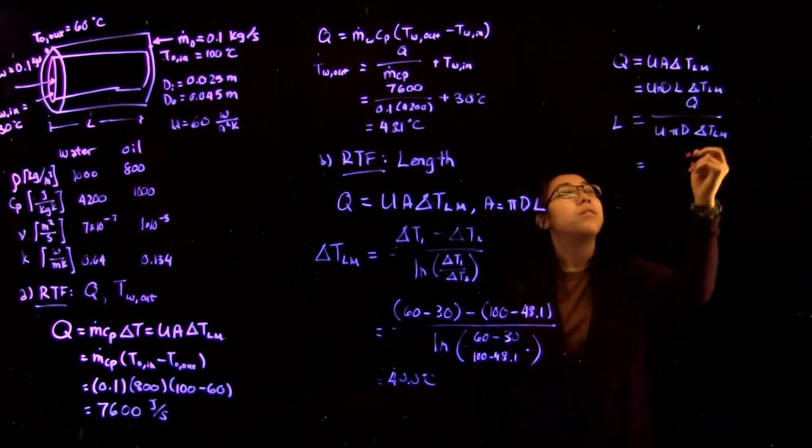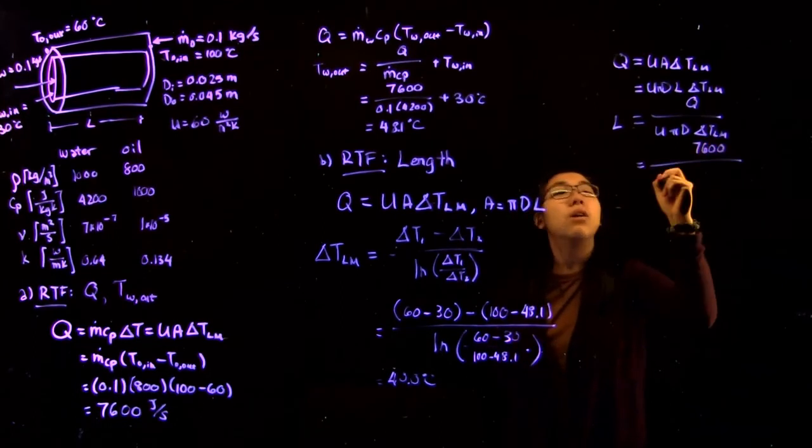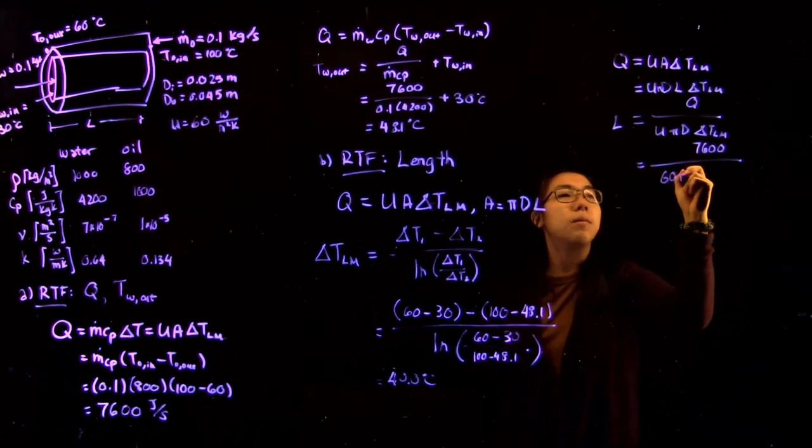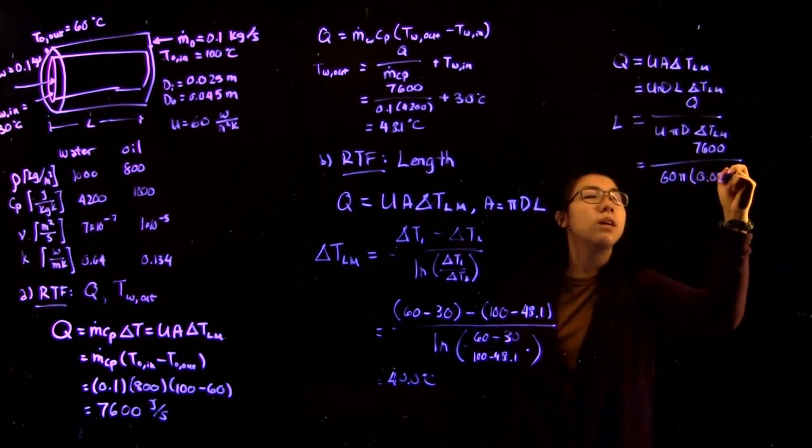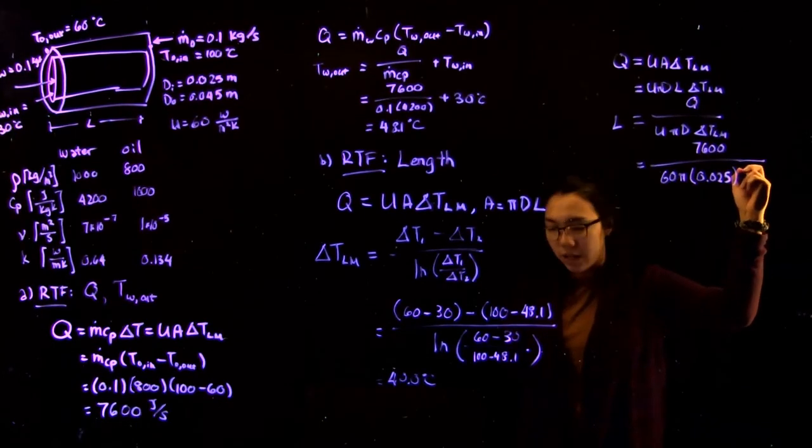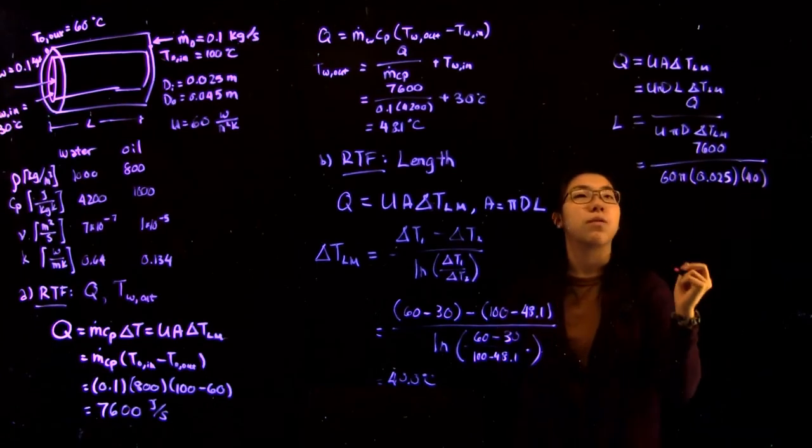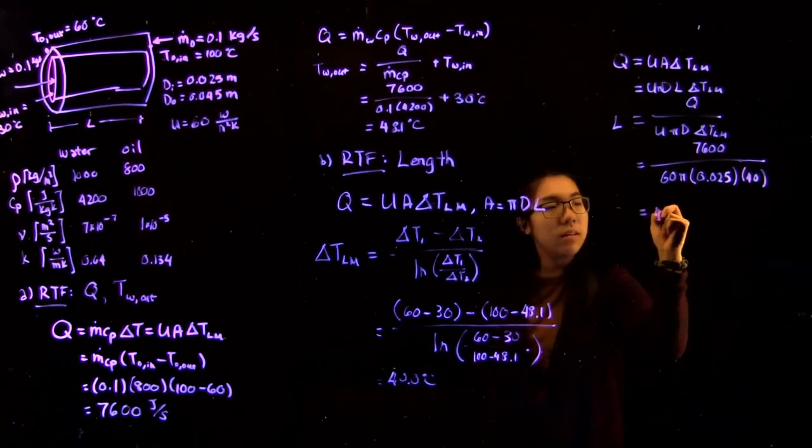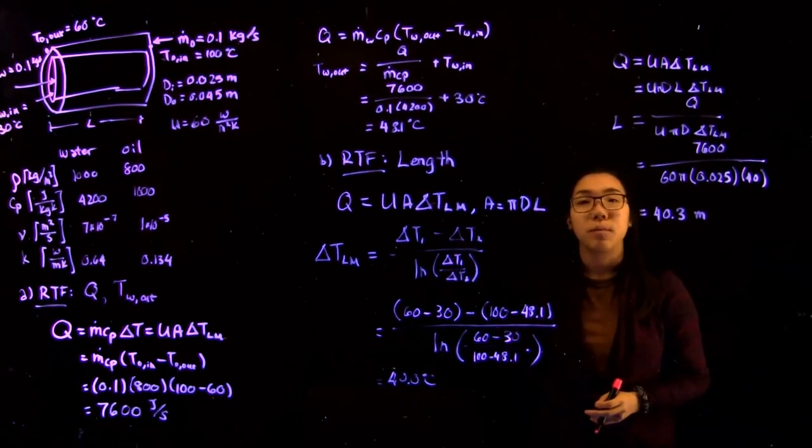And substituting in all our values gives 7600 over 60 times pi times the inner diameter, which is what's important to us, 0.025, times the log mean temperature of 40. And this gives us a final exchanger length of 40.3 meters.